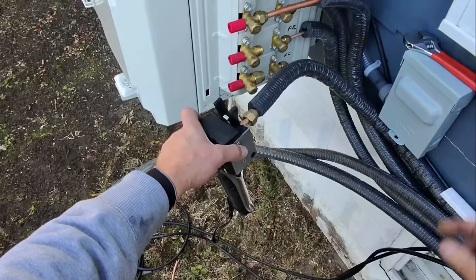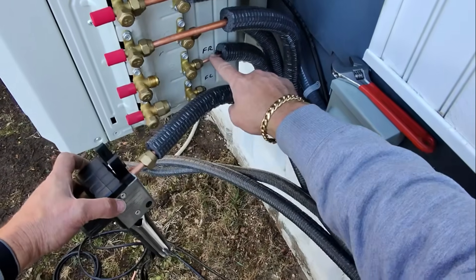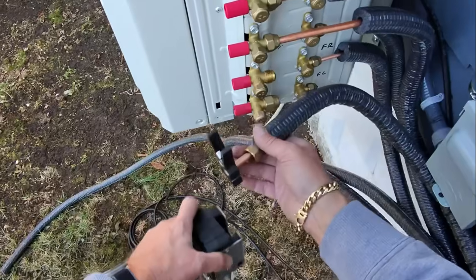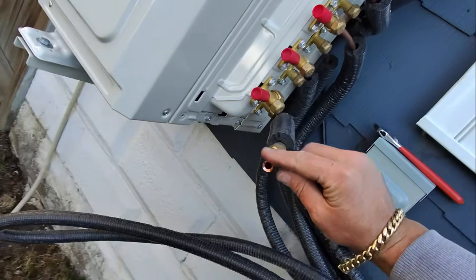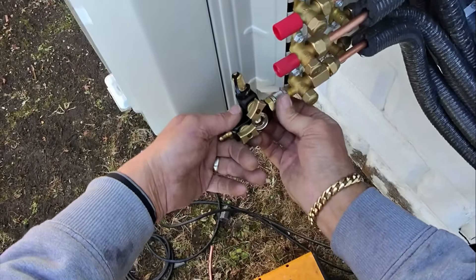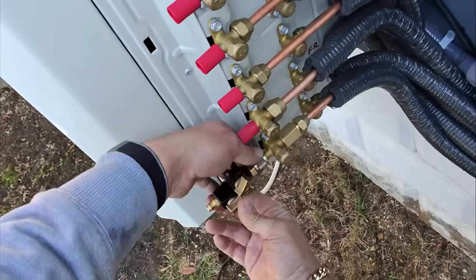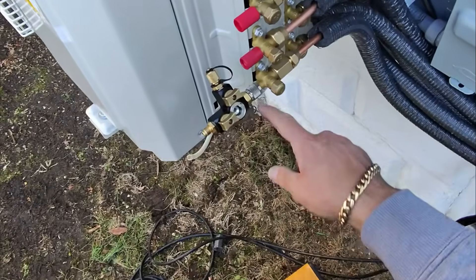From the outdoor unit, terminals one, two, three, and ground — those four connectors go to the terminals on the main control board. Right now we're flaring the three-eighths line for the front right room, which is the living room on the second floor of this two-family house. It makes a perfect flare every single time. I'm also using this Fieldpiece Schrader core removal tool — I like it because it lets you see when you take the Schrader core out of the body.